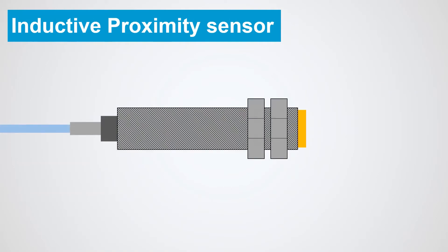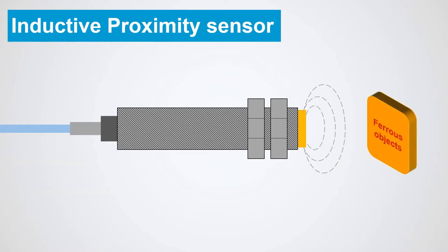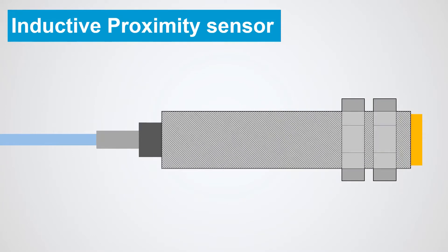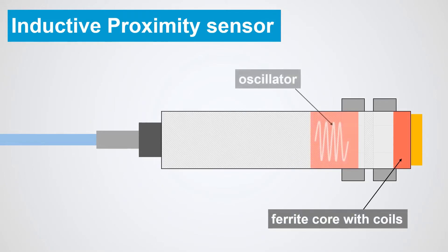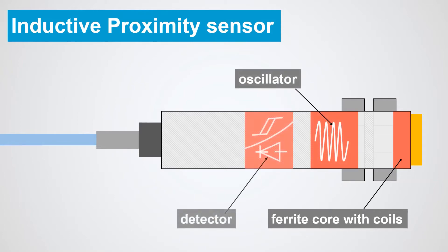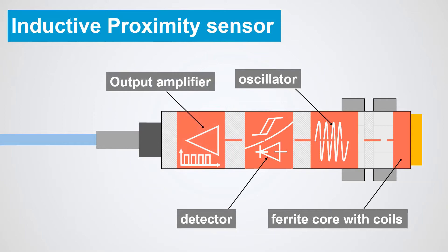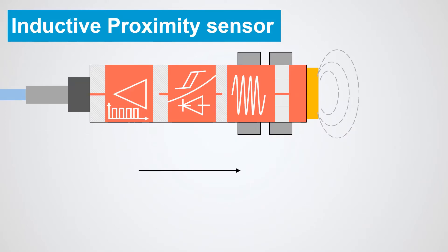An inductive proximity sensor is a non-contact proximity sensor that can detect ferrous objects that contain iron, ideally mild steel thicker than one millimeter. It consists of four major components: a ferrite core with coils, an oscillator, a detector or signal conditioner, and an output amplifier, all packed in a compact housing.